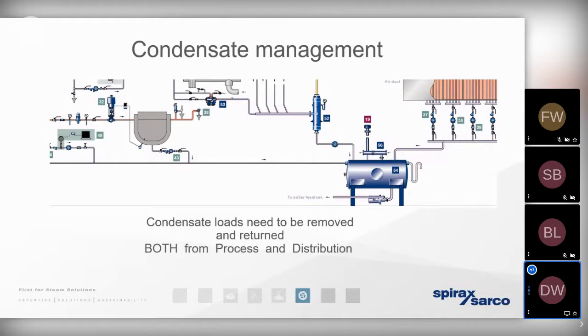having a look at the condensate side, the condensate network. So we know condensate exists wherever steam gives up its heat energy. That can be in the distribution pipework, or it can be at the process. The important thing to bear in mind is that we need to recognize the value of that condensate and get it back to the boiler house.